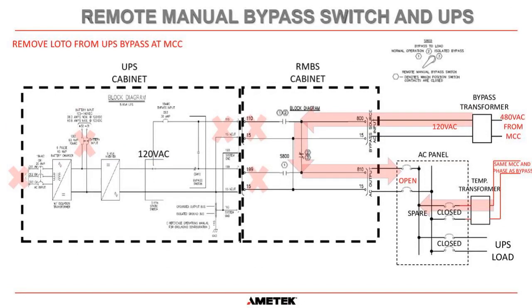So now what you can do is remove the lockout/tagout from the UPS bypass at the MCC. So we can now energize the 480 volts. That will allow power to go down here through that contact and back out here. Remember, this breaker is still open and we are feeding the load circuits through this way here. But now we're getting ready to go back to normal operation. All the wires have been connected and everything is good. And our RMBS is still in position 3.